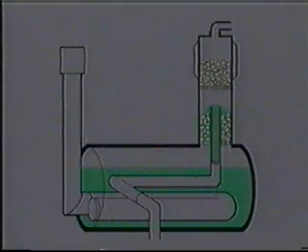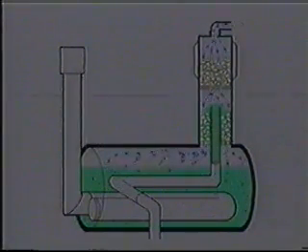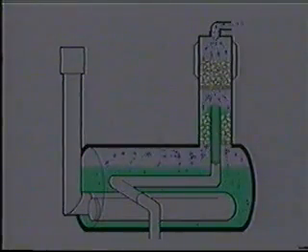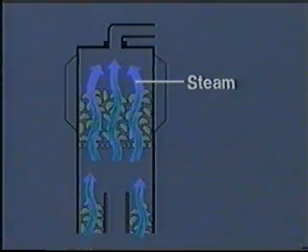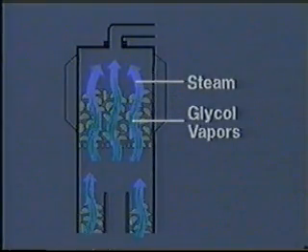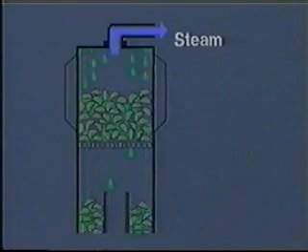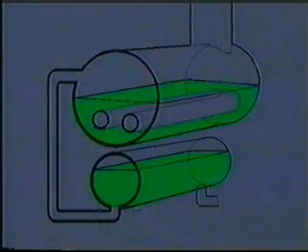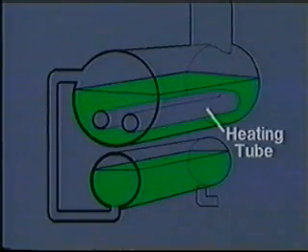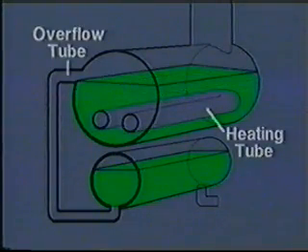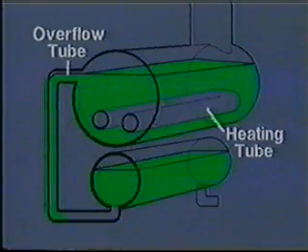As the glycol begins to heat, the water trapped by it begins to boil and moves upward through the still column as steam. Mixed with the steam will also be some hot glycol vapors. As this mixture passes upward through the still column, it comes in contact with a cooler part of the column, and the glycol vapors condense and drop back into the reboiler. The water leaves the top of the still column as steam. As this process continues, glycol in the reboiler accumulates above the heating tube until it eventually reaches the level of an overflow tube. The dried, purified glycol then spills into the overflow tube and into the surge tank once again.